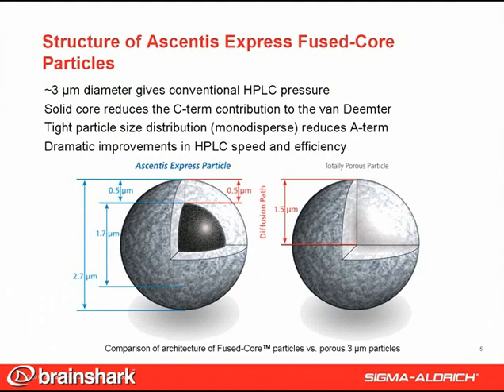And if you have a UHPLC instrument, you can run it faster or use longer columns than you can with sub-2-micron particle columns. Secondly, the Ascentis Express particle has a 0.5-micron shell around a solid core. This has mass transfer implications — it allows faster mass transfer and a smaller C-term in the Van Deemter equation, because the shorter 0.5-micron diffusion path into and out of the porous layer is about one-third that of the totally porous particle, so we can run at higher flow rates without loss of efficiency.